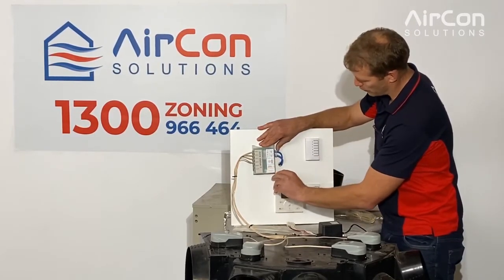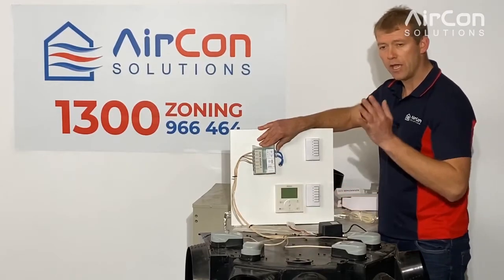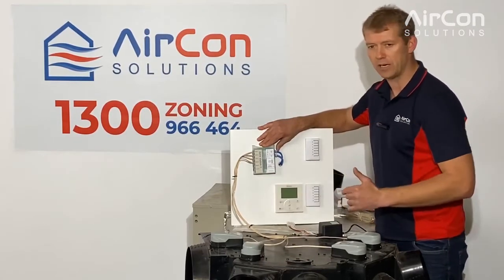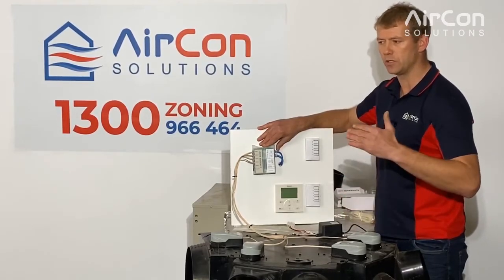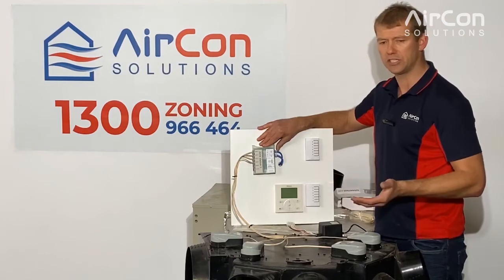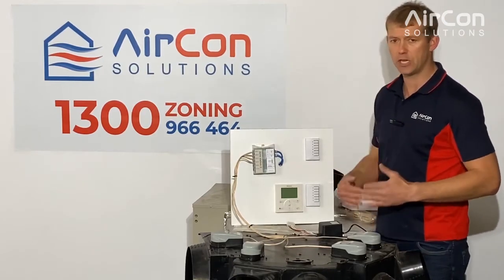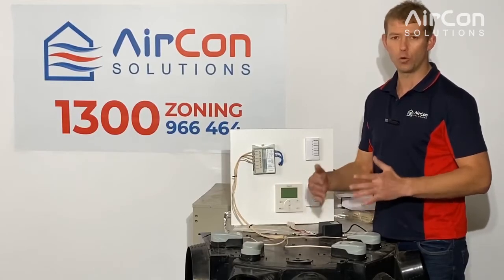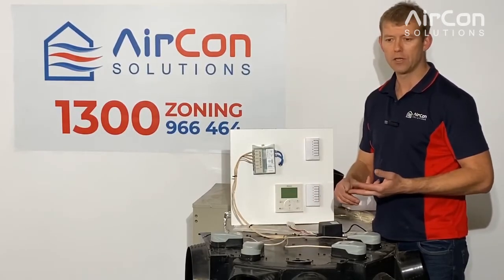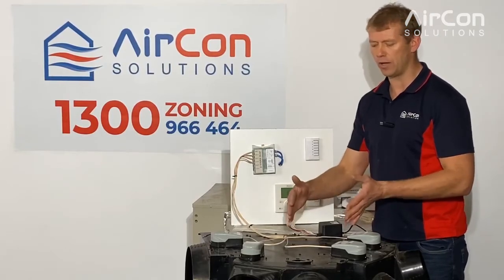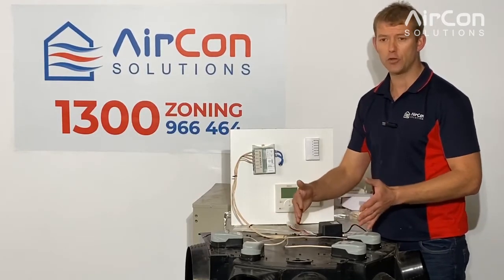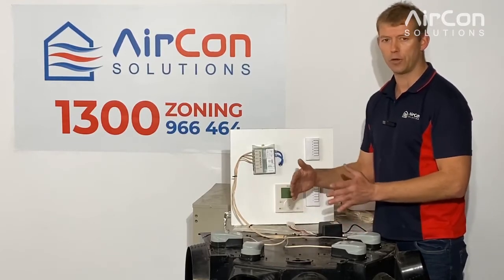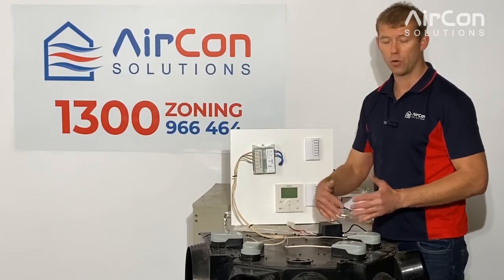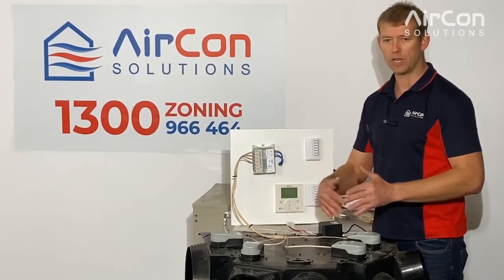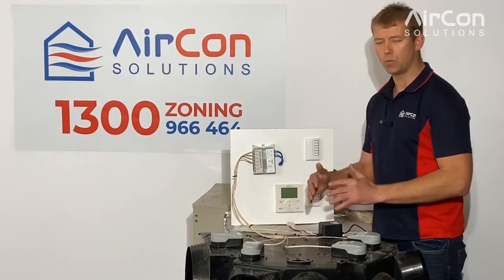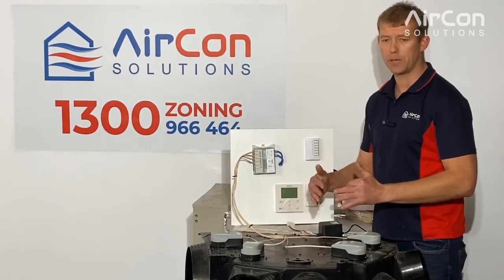Then down the bottom here, we've got a number of program constant zones. So if you've got a zone motor on every duct of the home, then we need to make sure that we set a constant. If a constant's not set, then the problem you're going to have is you have the potential to turn off every duct in the home, which is going to cause damage either to the ductwork or to the unit. So if you have a number of outlets that are not zoned, then you can get away with not putting on a program constant. But if they are all zoned, all outlets are zoned, and you have the potential to turn every outlet off, then we need to set at least 1 zone, sometimes maybe 2, depending on the size of the unit.